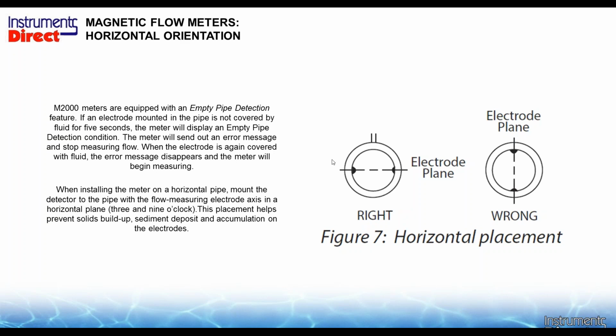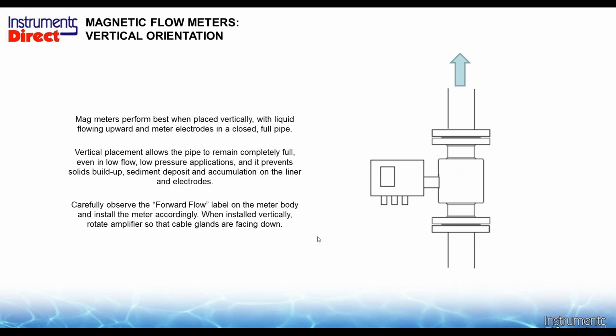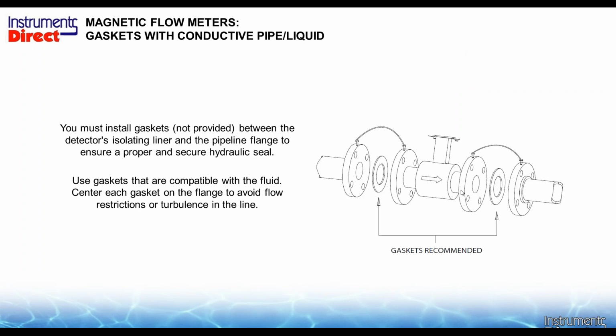If you were to install it on a horizontal application, the 3 and 9 o'clock electrode position is best. The top and bottom are wrong, just in case you get a lot of crud on the bottom of the pipe and air bubbles on the top. A vertical position really doesn't make that much difference. Should you have a vertical installation, no problem, a vertical installation is fine. I recommend you use it when the flow is going up. Flow falling down is a secondary choice, and every once in a while you get an application with flow going down, and depending on whether it's open to atmosphere, it can pull a lot of air and solids in there, and might not give you the best accuracy for your application. So if you have a choice on a vertical application, flow up is my first choice.